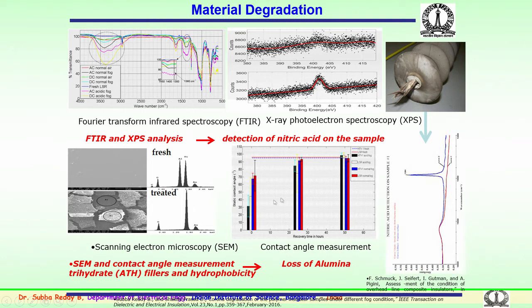Similarly, contact angle measurement is very important. Hydrophobicity performance of the insulators has been measured over a period of time, and this has been very clearly given here for various types of materials and their performance over a period of time. So, fresh, with moisture and with acidic fog, the performance has been seen and how the recovery has happened over a period of time. So, recovery time versus the static angle, that is the angle which the sample shows when the water droplet is being put on the rubber sample.